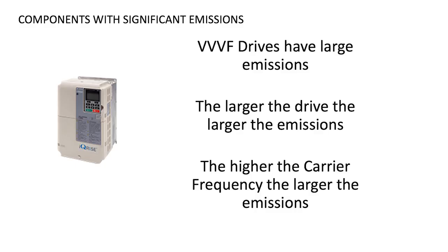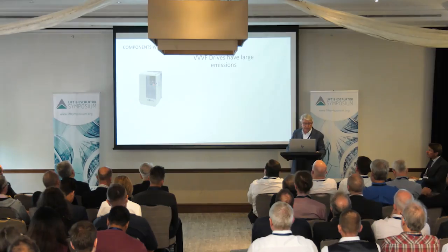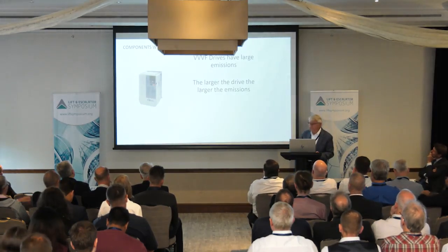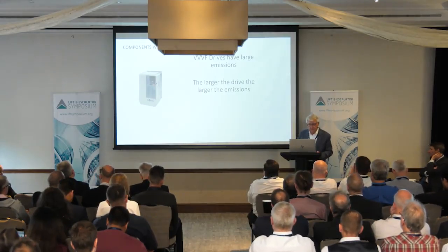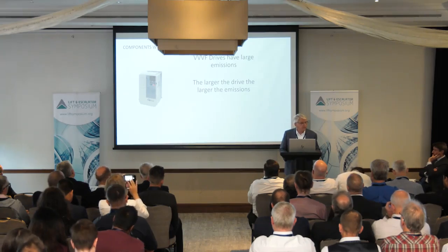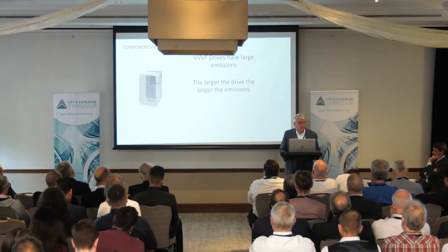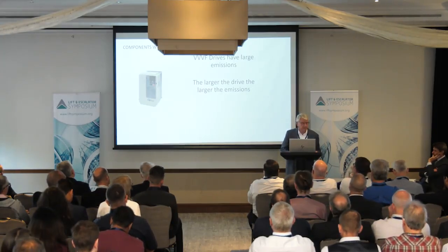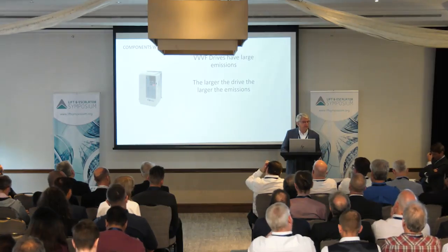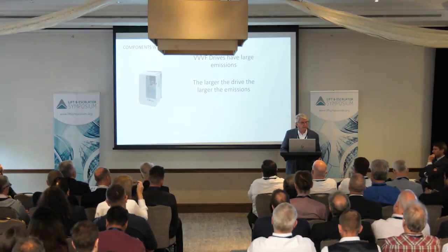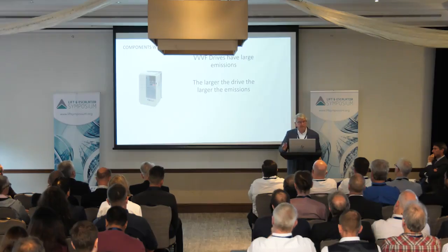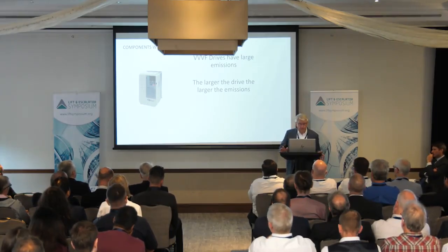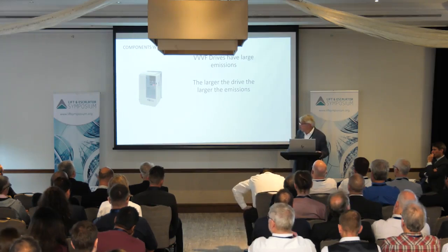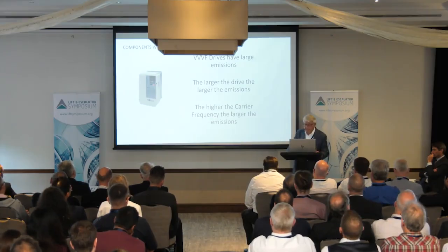What are some examples of components with significant emissions? VVVF drives are a big source, and the larger the drive, the larger the emissions. Also, the higher the carrier or chopping frequency, the higher the switching transients. Early inverter or VVVF drives had a switching frequency of 3 kilohertz; today 10 kilohertz is standard, with some going up to 16. The higher the frequency, the smoother the sine wave coming out of the drive, but also the higher the switching transients and the more problems they can cause. So higher frequency means larger emissions.